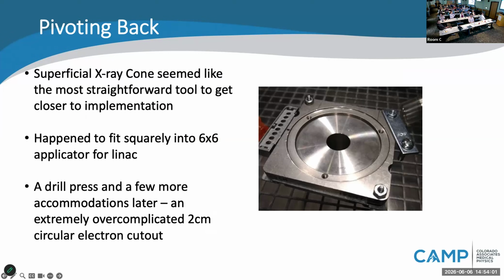So we went back to the drawing board a little bit and saw that our superficial X-ray cones really fit into a 6x6 applicator on the machine remarkably well. So that's a picture of a 2 centimeter electron or superficial X-ray cone sitting really squarely into that 6x6 applicator for the Linac. And with the garage shop mentality, a drill press, and a couple of trips to ACE, we were able to make something that would actually fit into the machine.